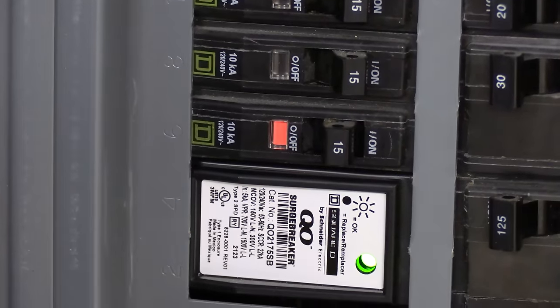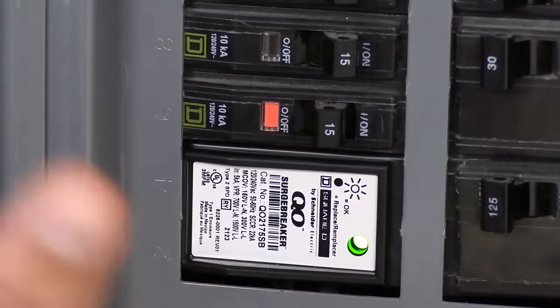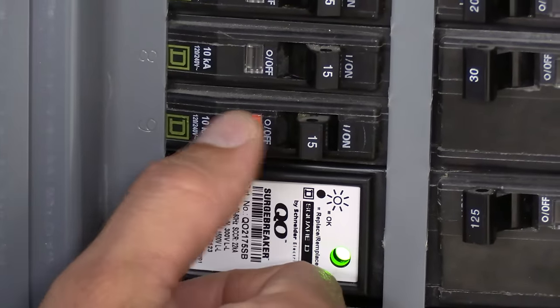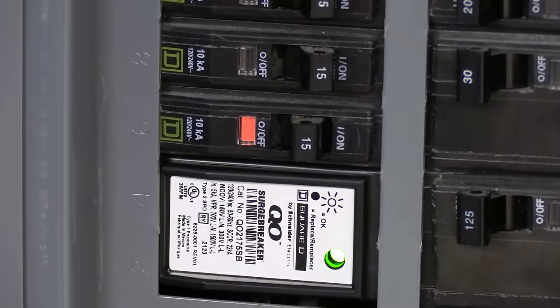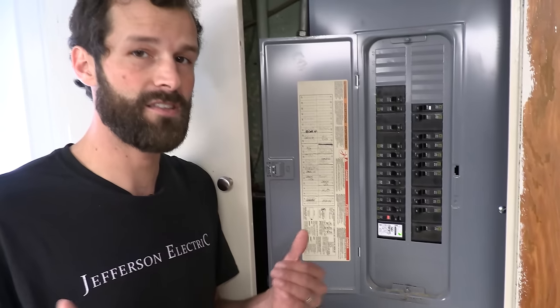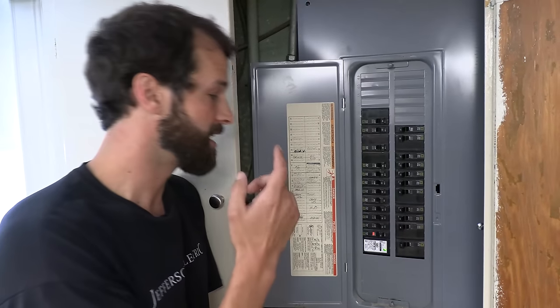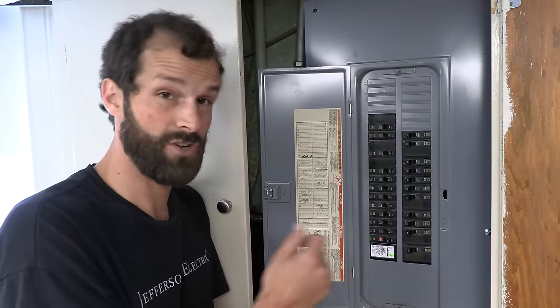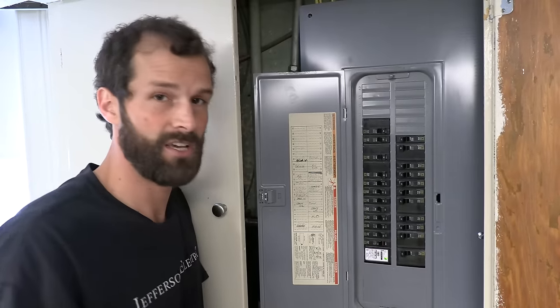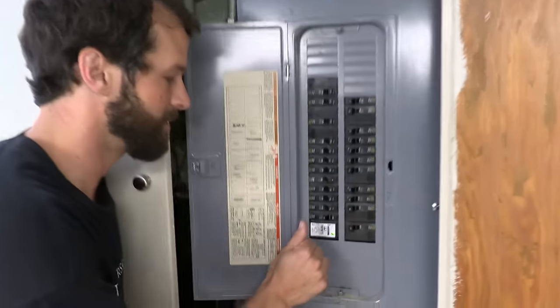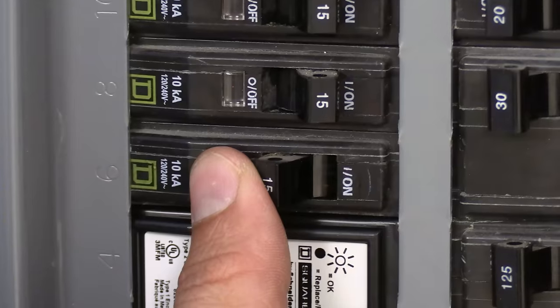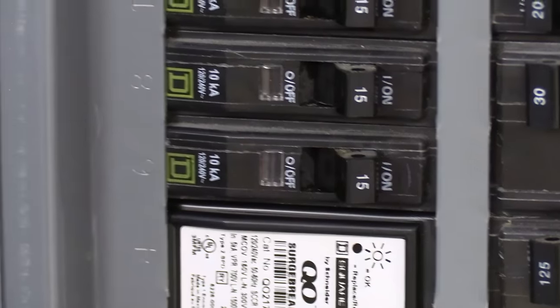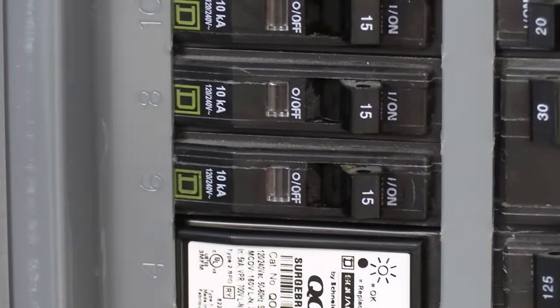And where homeowners have occasionally gotten confused, and you've got to rehearse this with them on the phone, even though it sounds rudimentary, is they're like, the breaker won't go on. Well, if there's a faulted breaker, you've got to check the cause of the fault before you reset it. There's a ton of power that's going to surge through there if you just sit there and try to just reset it. And when you reset it, you move it to the off position. You investigate for cause of fault. And then when fault is cleared, you reset to the on position. Fault is now cleared. Back to the on position. Red flag goes away. And breaker's nice and tight.